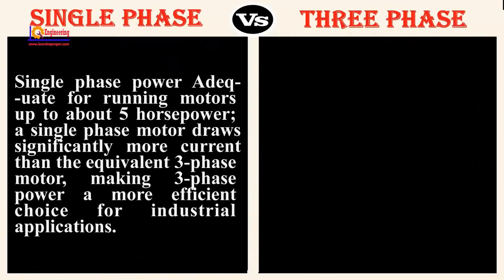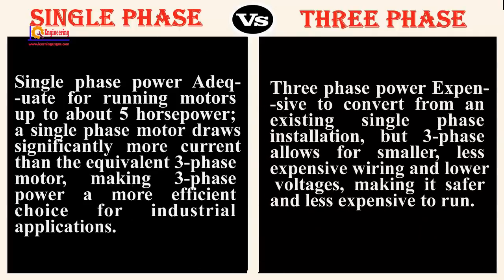Single-phase power is adequate for running motors up to about 5 horsepower. A single-phase motor draws significantly more current than the equivalent three-phase motor, making three-phase power a more efficient choice for industrial applications. Three-phase power is expensive to convert from an existing single-phase installation, but three-phase allows for smaller, less expensive wiring and lower voltage, making it safer and less expensive to run.